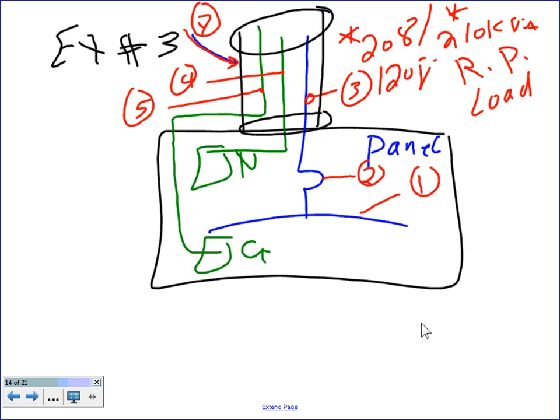Since it's a receptacle panel and we are in Minnesota, the voltage that we use for receptacles is 120, and 208 is the line-to-line voltage, right? We burn our receptacles in the US at 120. If we're burning them at 220, it would be 380/220.